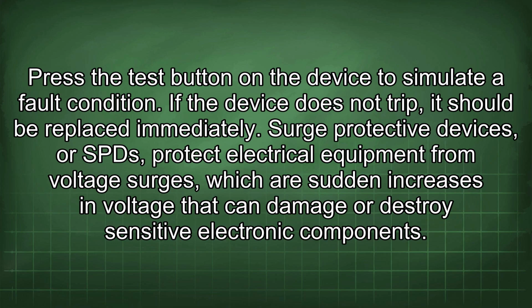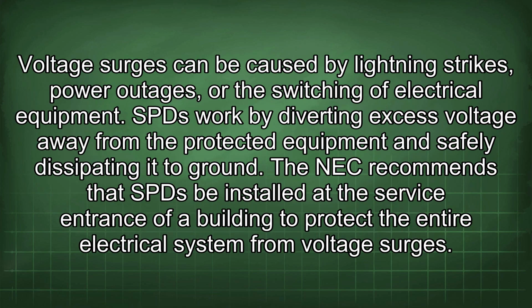Surge protective devices, or SPDs, protect electrical equipment from voltage surges, which are sudden increases in voltage that can damage or destroy sensitive electronic components. Voltage surges can be caused by lightning strikes, power outages, or the switching of electrical equipment. SPDs work by diverting excess voltage away from the protected equipment and safely dissipating it to ground.